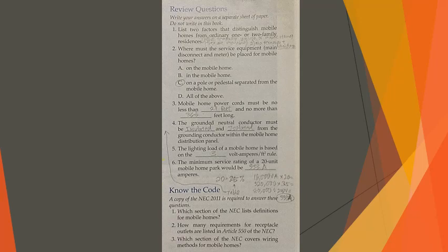And that is how you go about finding that out. 16,000 VA times 20, or 320,000, times 0.25 or 25%, which is 80,000. You divide 80,000 by 240 volts, gives you 333 amps. Moving on to the Know the Code section. Number 1, which section of the NEC lists definitions for mobile homes? And that is Article 550, page 70-481 of the 2011 NEC.